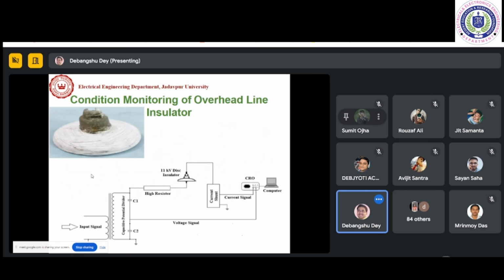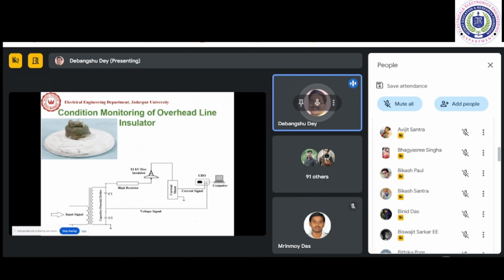Another example is condition monitoring of overhead line insulators. There are so many insulators that manual checking of each one is not possible. So if we can have a signal recorded on site and processed locally, we can have an automated setup that avoids manual intervention for checking every insulator's condition. If insulators are very aged or polluted, surface leakage current becomes high, which can cause a dead short circuit. This is a laboratory setup.